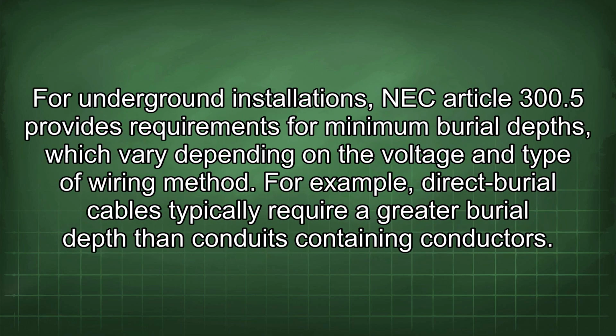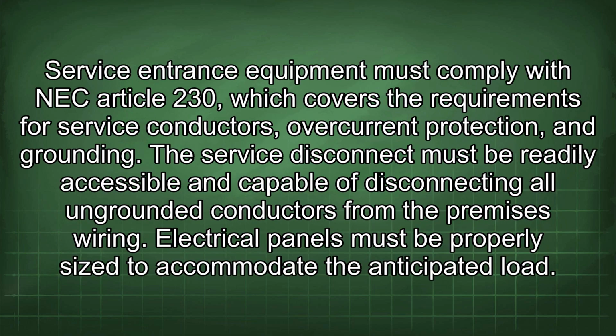For underground installations, NEC Article 300.5 provides requirements for minimum burial depths, which vary depending on the voltage and type of wiring method. For example, direct burial cables typically require a greater burial depth than conduits containing conductors. Service entrance equipment must comply with NEC Article 230, which covers the requirements for service conductors, overcurrent protection, and grounding. The service disconnect must be readily accessible and capable of disconnecting all ungrounded conductors from the premises wiring.